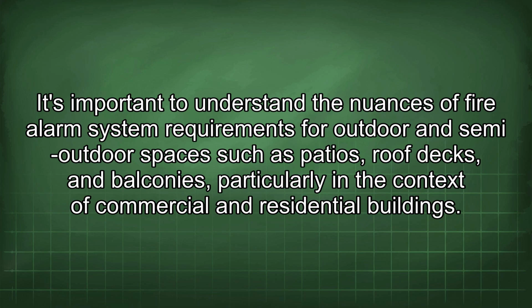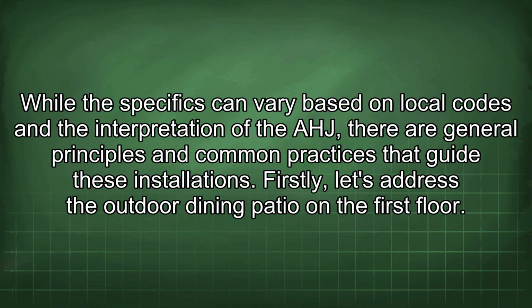It's important to understand the nuances of fire alarm system requirements for outdoor and semi-outdoor spaces such as patios, roof decks, and balconies, particularly in the context of commercial and residential buildings. While the specifics can vary based on local codes and the interpretation of the AHJ, there are general principles and common practices that guide these installations. Firstly, let's address the outdoor dining patio on the first floor.